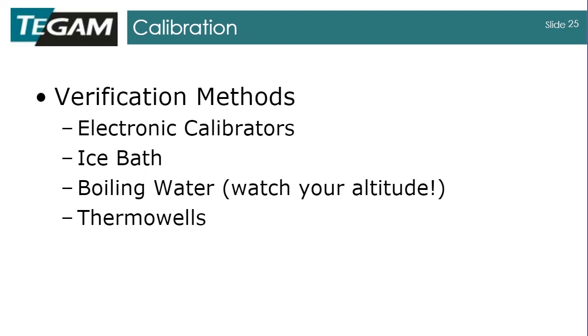Another way people do this is with a simple instrument called a thermal well—a small heated block with a hole in it where you insert a probe. The block's heat is maintained at a very static point, so you can validate your thermometer's reading against it. You can do this daily, weekly, or whatever fits your quality procedures and the rigors of your facility.